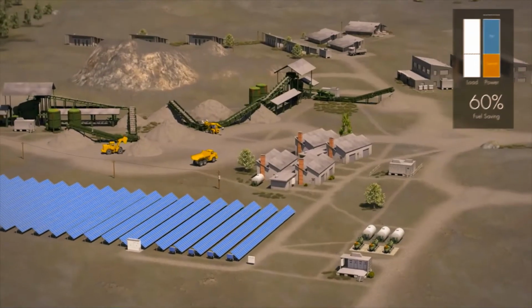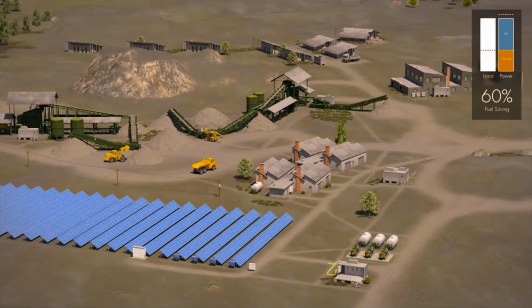The SMA Fuel Save solution automatically synchronizes the PV system with the diesel grid. All information, including grid properties, load requirements, and minimum genset loading, is taken into account when the SMA Fuel Save controller defines the optimal PV power set point.